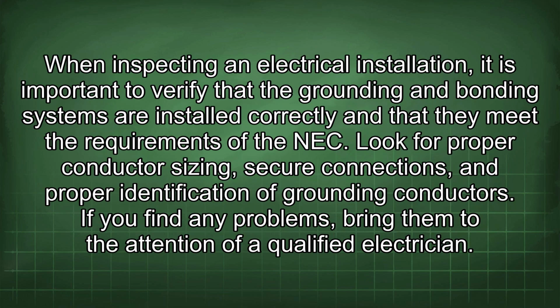When inspecting an electrical installation, it is important to verify that the grounding and bonding systems are installed correctly and that they meet the requirements of the NEC. Look for proper conductor sizing, secure connections, and proper identification of grounding conductors. If you find any problems, bring them to the attention of a qualified electrician.